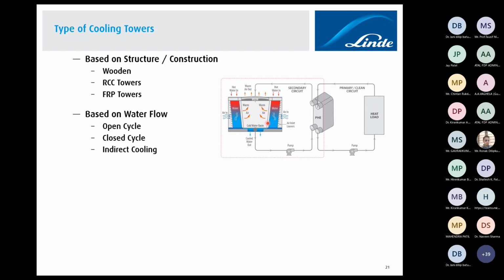And depending on the water availability, depending on the impurities present in the cooling tower water, you will have to design all your heat exchangers accordingly, and sometimes it is very costly, because it will call for you to go from carbon steel to alloy steel or sometimes stainless steel, and this is how the capital cost of heat exchangers increases. So rather than that, you put in one exchanger with superior metallurgy, and you just pass on the heat to the secondary circuit, and there in the secondary circuit you have your intended water.